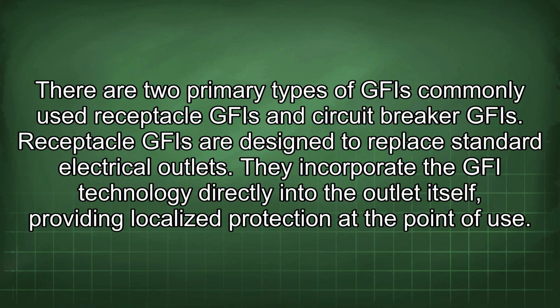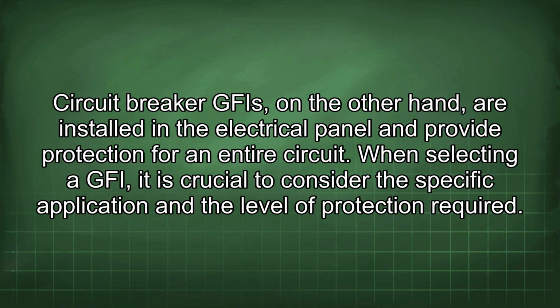There are two primary types of GFI commonly used: receptacle GFI and circuit breaker GFI. Receptacle GFI are designed to replace standard electrical outlets. They incorporate the GFI technology directly into the outlet itself, providing localized protection at the point of use. Circuit breaker GFI, on the other hand, are installed in the electrical panel and provide protection for an entire circuit.